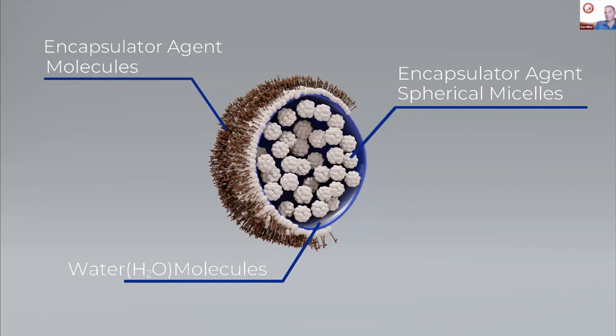Inside of the spherical micelles, as those are formed and flipped, inverted inward with the polar tails in, they're capturing gas as they're traveling through the air. They're capturing those carbons and hydrocarbon gases that would cause fire development and cause the atmosphere to be toxic. And then when they actually strike a liquid, like liquid electrolyte, they encapsulate that as well. So it's really a very unique chemical reaction that happens within a fraction of a second and puts out fires very, very rapidly and provides rapid cooling as well. Encapsulate.